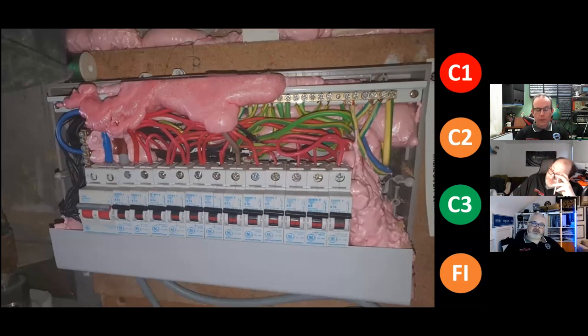I saw a job the other day where the person was using some pink foam filler that was fire rated. So I took a piece of it and I went outside into the car park and I set fire to it. Sorry, gives off black smoke. There's a place I'm going to tomorrow, actually. It's got a load of this in the riser. So I might just steal a bit and put a flame to it for about 30 to 60 seconds and just watch the black smoke come out.